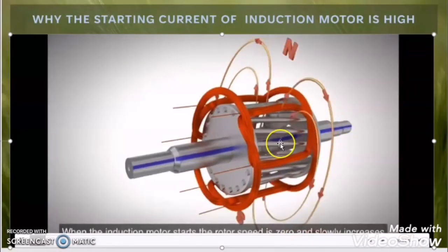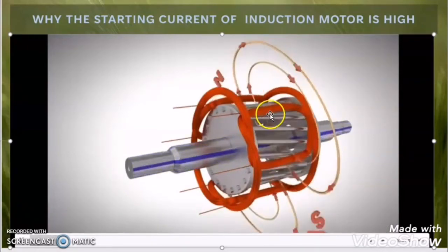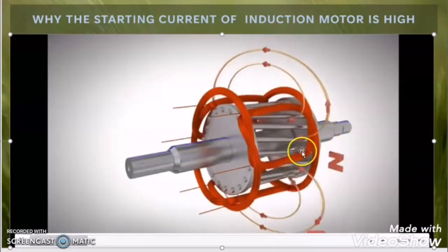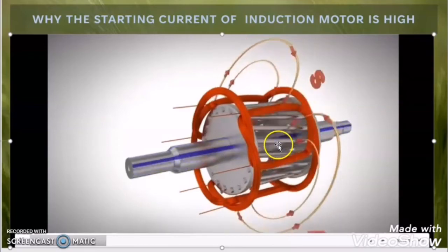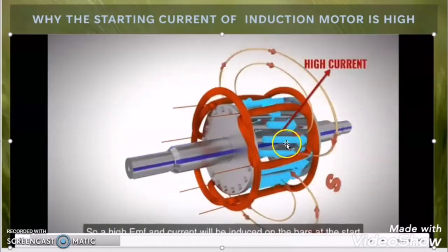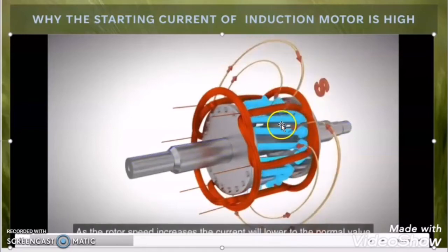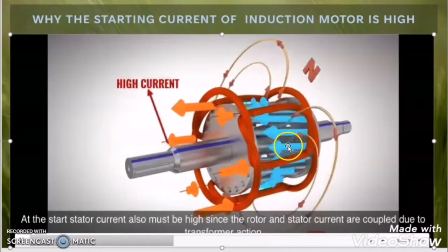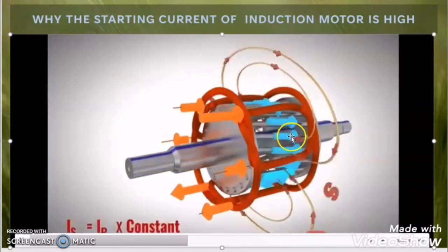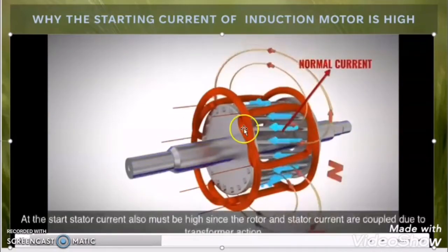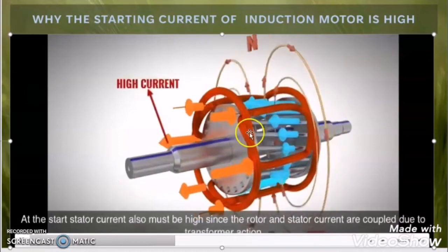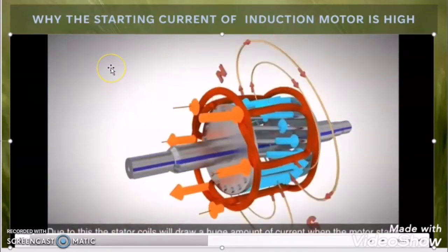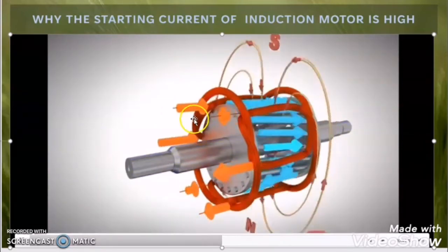At the time of starting, you can notice that the rotating magnetic field is rotating with the synchronous speed but the rotor bar is in the standstill position. So at the time of starting, there will be maximum flux linkage with the rotor bar, which will produce maximum induced EMF and induced current in the rotor bar. As the motor stator winding and the rotor is coupled with transformer action, when there is high induced EMF in the rotor bar, the motor will draw high inrush current at the time of starting.